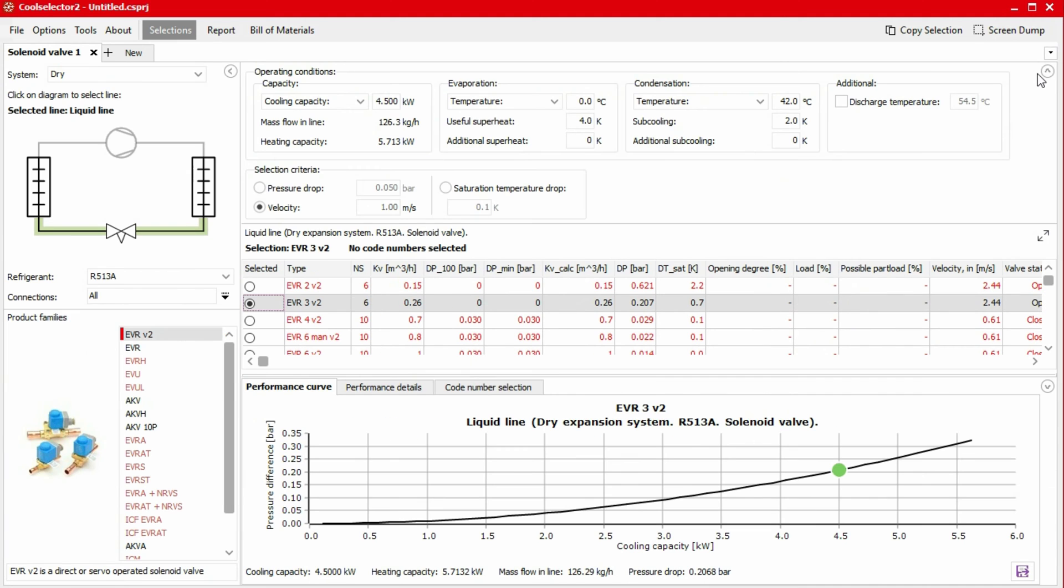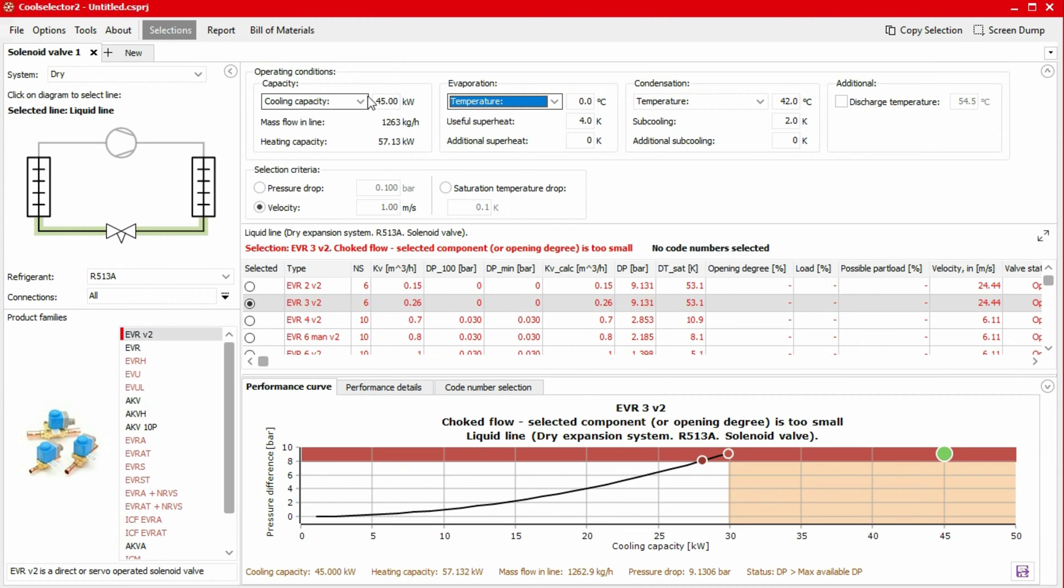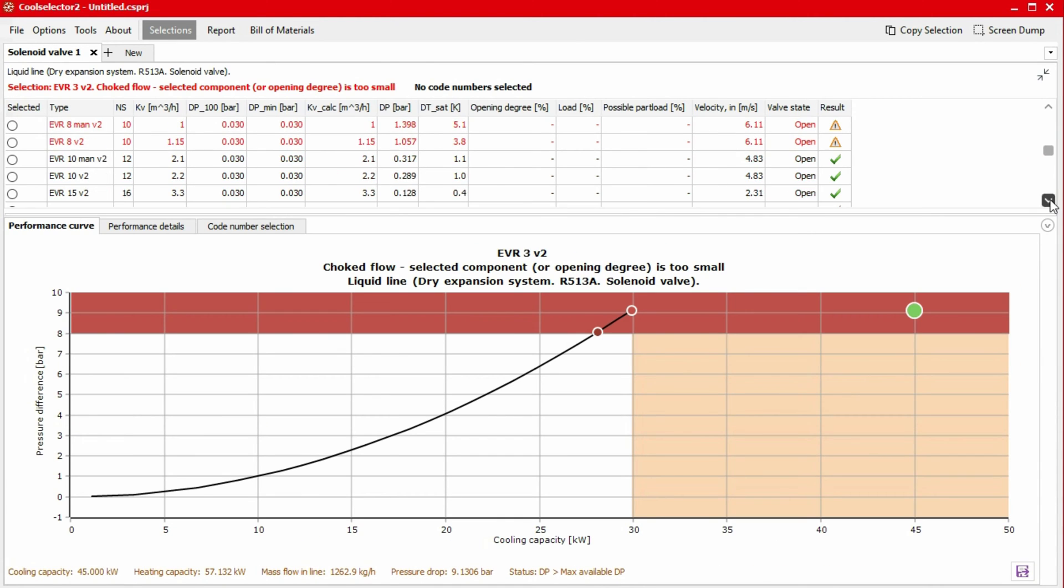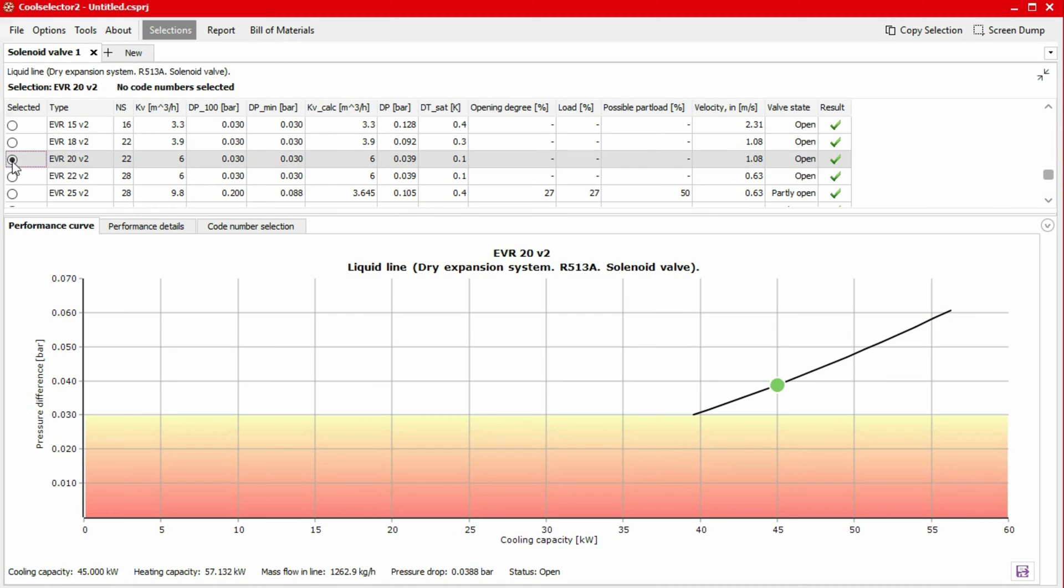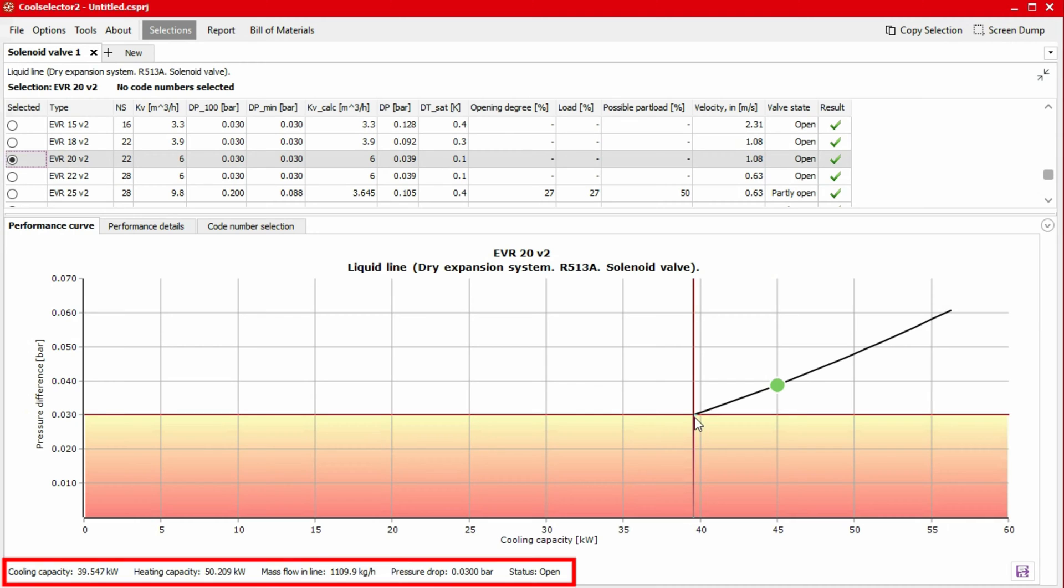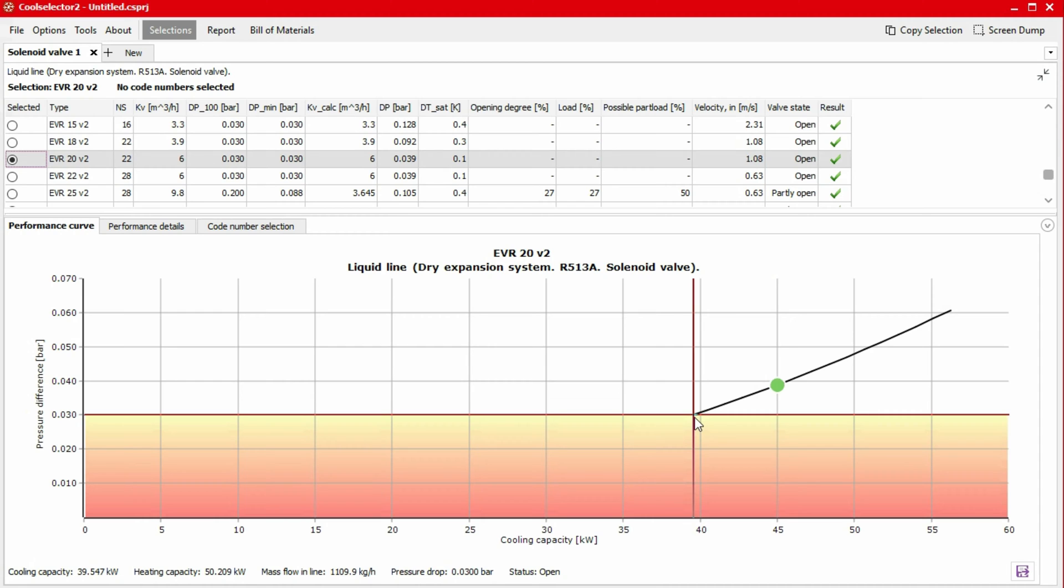If we change it back to our original capacity of 45 kilowatts and click on the suggested product, we can see the performance curve has a lower limit. We can see here that the valve is not suitable for an application lower than 39.5 kilowatts. And in our case, that's 87% of the nominal load.